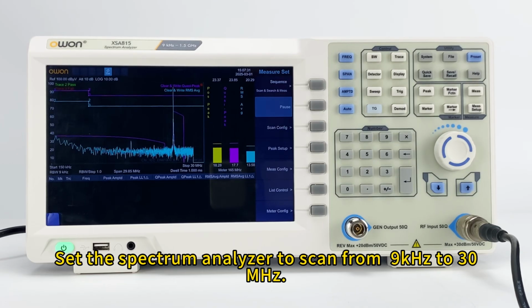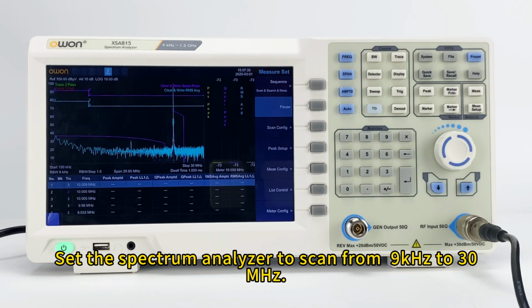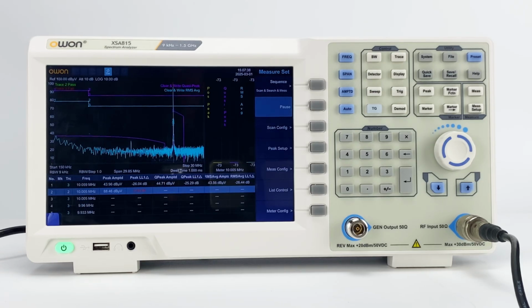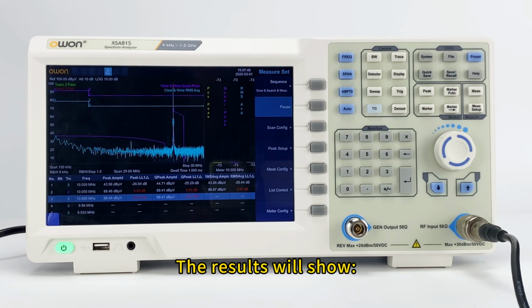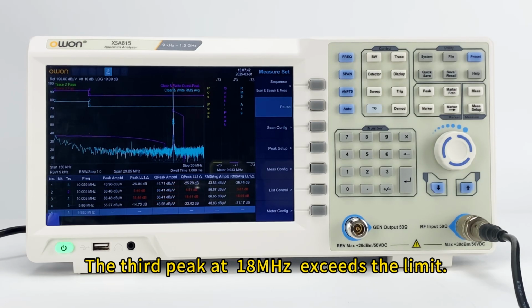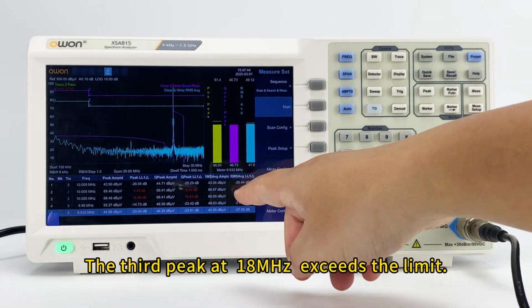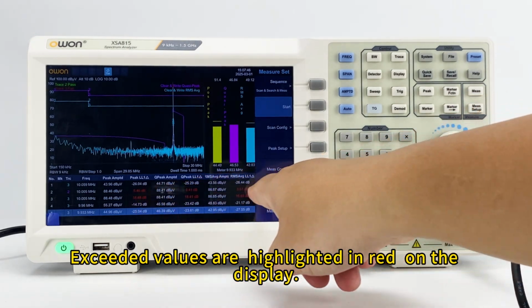Set the spectrum analyzer to scan from 9 kHz to 30 MHz. The results will show. The third peak at 18 MHz exceeds the limit. Exceeded values are highlighted in red on the display.